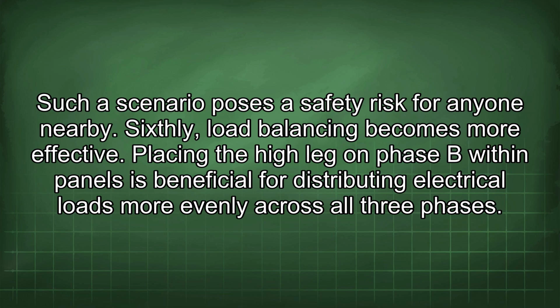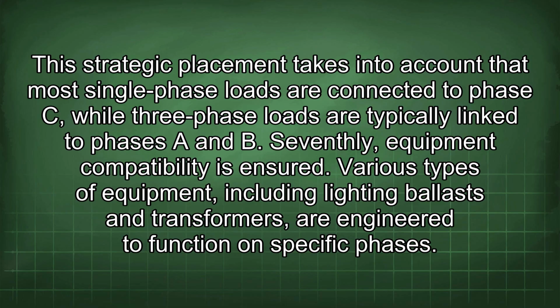Sixthly, load balancing becomes more effective. Placing the high leg on phase B within panels is beneficial for distributing electrical loads more evenly across all three phases. This strategic placement takes into account that most single-phase loads are connected to phase C, while three-phase loads are typically linked to phases A and B.